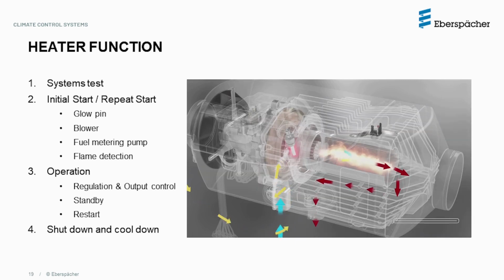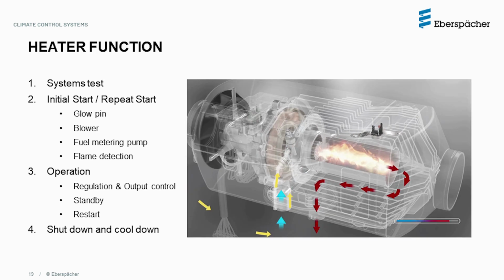When the fuel begins to burn independently, the temperature of the heat exchanger will rise. This will be measured by the flame sensor, and the ECU will be able to detect the flame. The glow pin will be switched off shortly afterwards. Like the first generation heaters, if the Airtronic 2 heater is not successful in the first attempt, it will automatically make a repeat start attempt. But if the 2 consecutive start attempts are not successful, the heater will generate an active fault code and go through a cool down cycle before switching off.